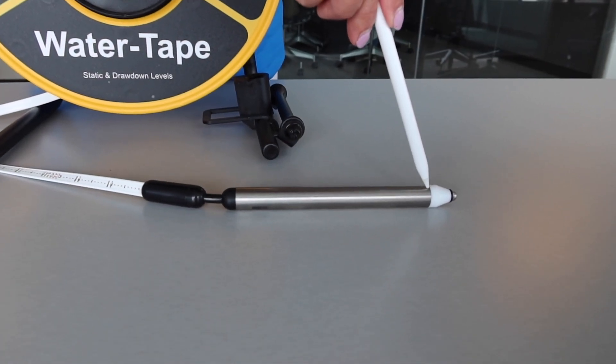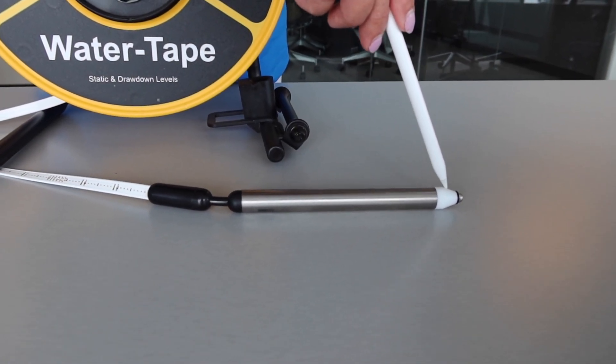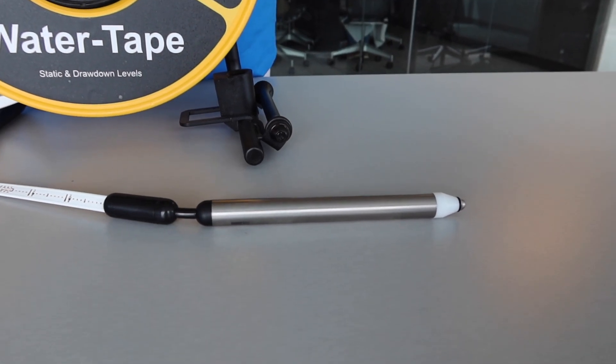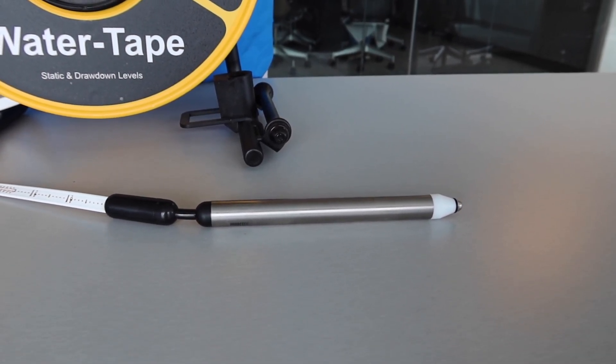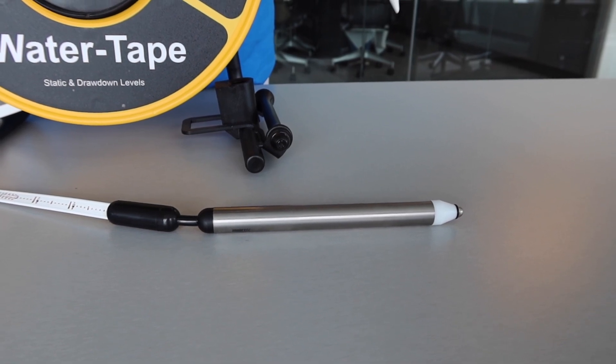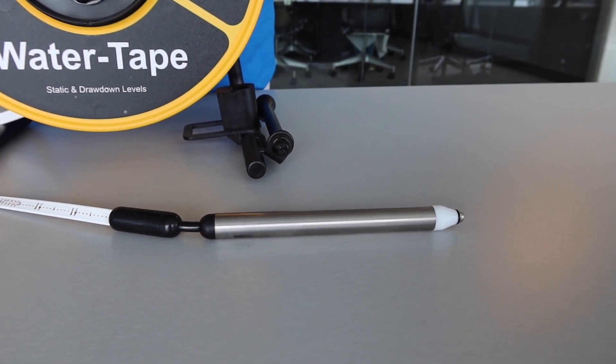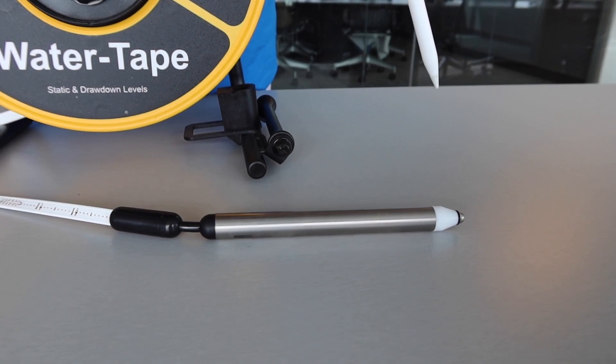Please note that you need to have both the stainless steel end as well as the start of the probe body submerged in the water. This creates complete contact with the circuit and activates the signal. The probe body is the start of the first foot or meter mark. The zero point starts here.